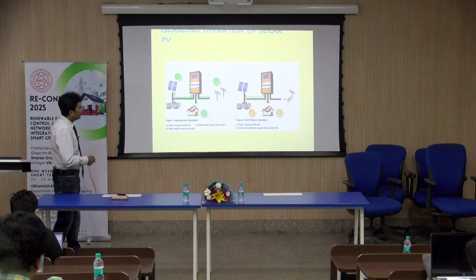Suppose this is my system. This is my solar PV. It is connected to my inverter and it is connected after net metering to my utility. Understand that, suppose imagine a situation when there is a problem in the utility. In that case, that power is not here. That system becomes islanded and it will be supplying within house in an islanding mode.